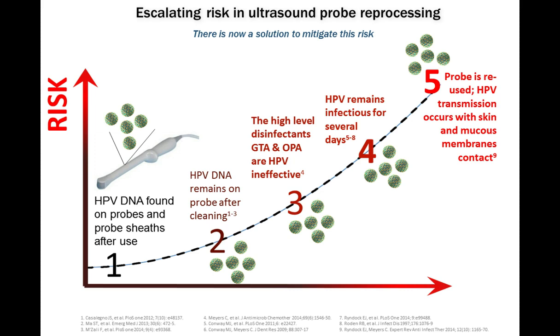So the escalating risk of ultrasound probe reprocessing. You can look at this chart we've put together. This is how we see the escalating risk. HPV DNA is found on probes and probe sheaths after use. HPV DNA remains on probes even after cleaning procedures are done. High-level disinfectants, GTA and OPA, are ineffective at deactivating or killing HPV. HPV can remain infectious for several days on an inanimate surface. And if the probe is reused, HPV transmission can occur with skin and mucous membrane contact.